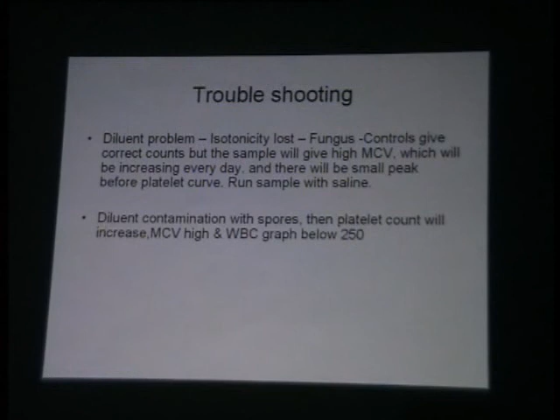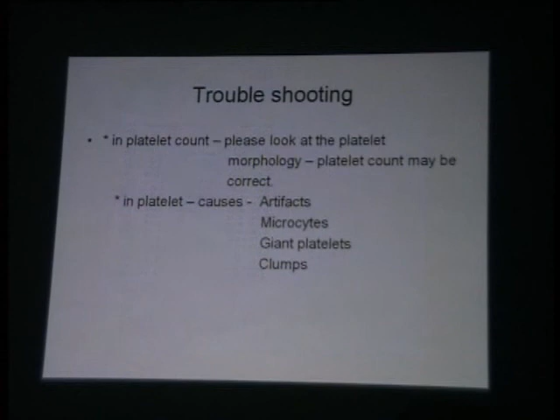The platelet count should be looked at morphologically, as I said, because it may be due to artifacts, microcytes. Next. No, the previous one. This one. Calibrator should be run once a year. These are machines after all. You have to respect them. You have to make proper use of them. Run your calibrator once a year, NABL says. Run 3-level controls every day.